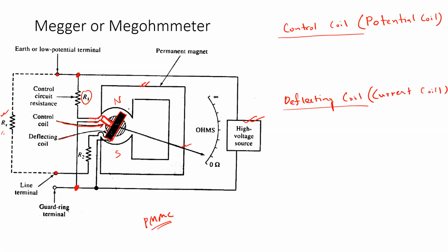On the other hand, the potential coil is almost in parallel with the supply voltage and also in parallel with the load. In that sense, you can call it the potential coil. Now the two current limiting resistors are necessary to limit the magnitude of current flowing through both the control coil and the deflecting coil, because for high resistance measurement, a high voltage source is necessary. If the current limiting resistors are not placed, the windings will burn out. So these two resistances have to be put there, and between the two windings a magnetic core is placed so that the magnetic permeability can be enhanced.